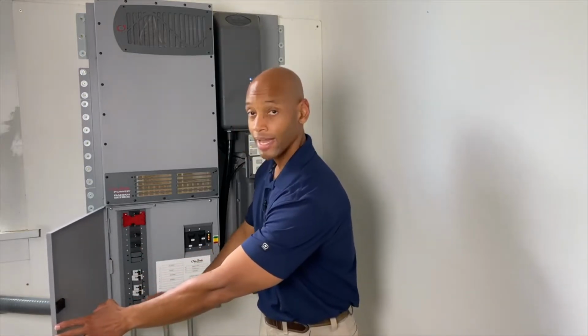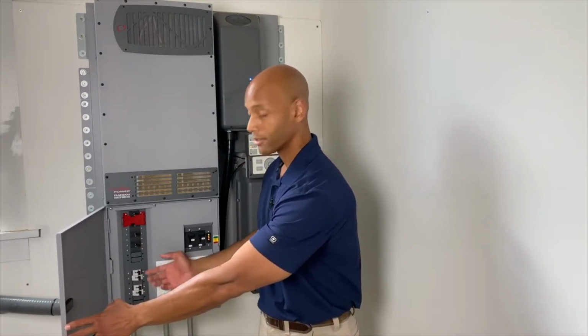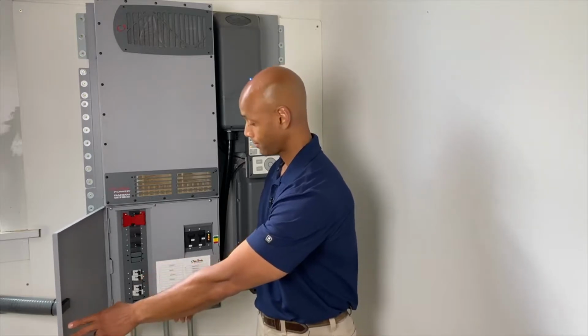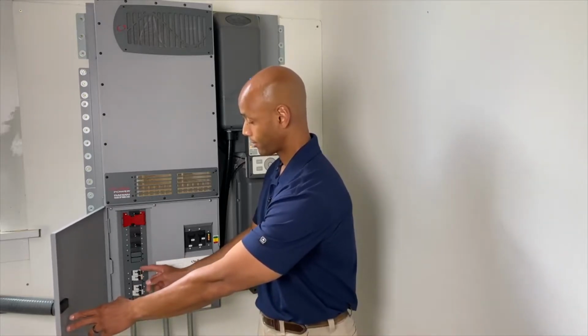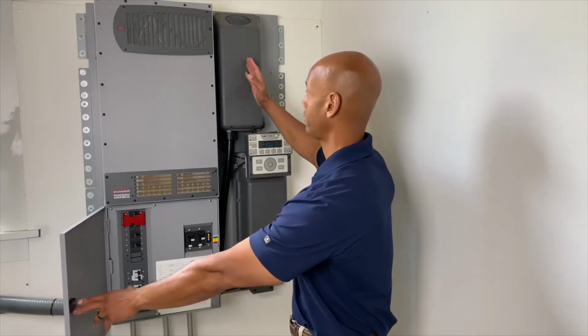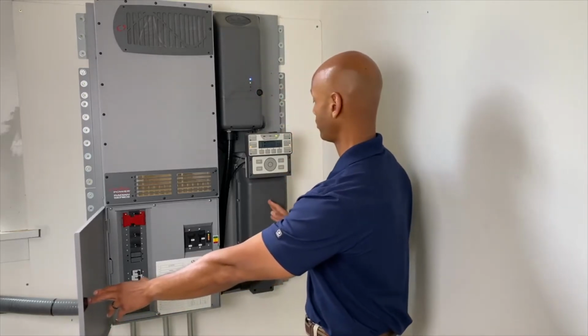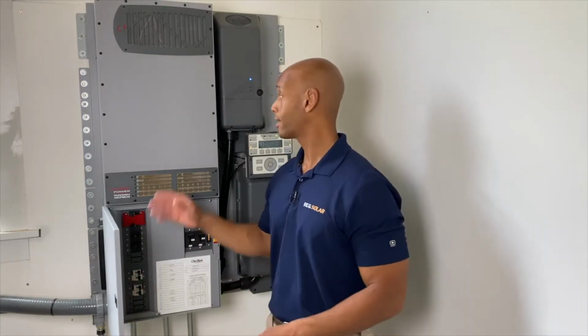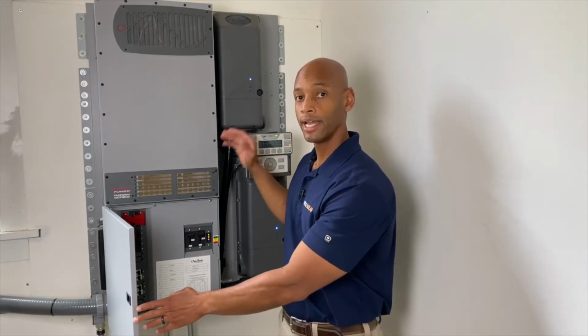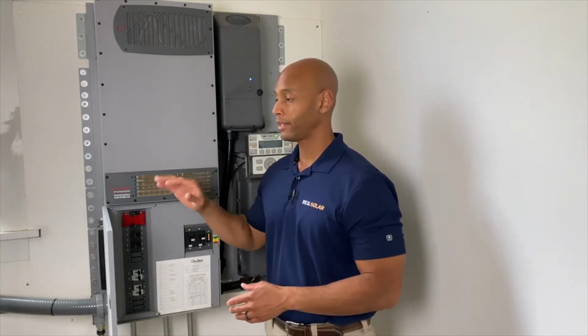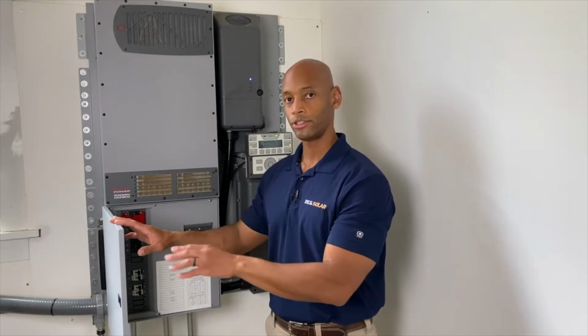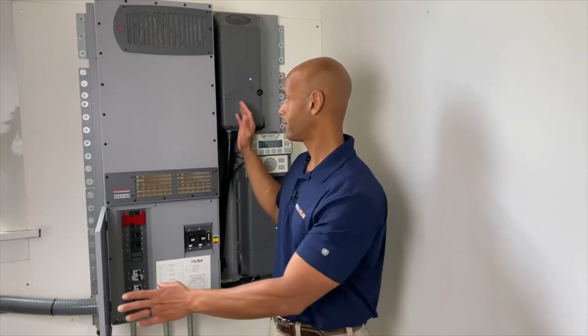On the bottom half of the switchgear, these are your DC circuit breakers, one for each charge controller. So you've got a charge controller here and here. Think of the charge controller as a solar battery charger. Solar power comes into the charge controller unit, and it steps the voltage down to the optimal level to charge your battery bank. That's the main purpose of the charge controllers.